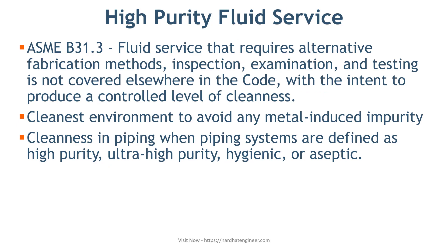The fifth fluid service is high purity fluid service. ASME B31.3 says that a fluid service that requires alternate fabrication methods, inspection, examination, and testing not covered elsewhere in the code — with the intent to produce a controlled level of cleanness — falls in this category. When the process fluid requires the cleanest environment to avoid any metal-induced impurity, additional standards are used to design this piping. Industries such as pharma and food processing may require this type of cleanness, when piping systems are defined as high purity, ultra-high purity, hygienic, or aseptic.